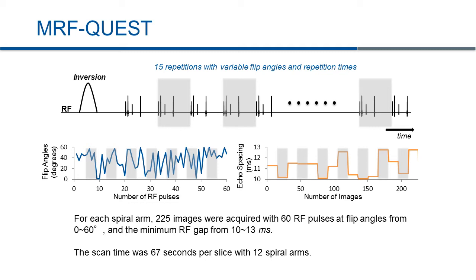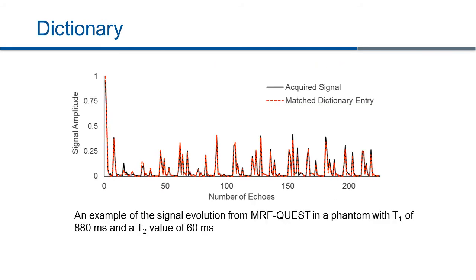With these acquisition parameters, we calculated the dictionary using Bloch simulations with a range of T1 and T2 values. Here is an example of signal evolution at T1 of 880 milliseconds and T2 of 60 milliseconds. A complex inner product was used to match the acquired signal to each entry of the dictionary. The entry with the maximum inner product is selected to represent the acquired signals. The black curve represents the acquired signal and the dotted red curve is the matched dictionary entry.